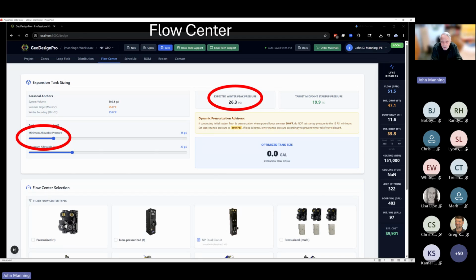And this is the nature of polyethylene pipe. And the program takes into account all the dynamics, the different modulus of elasticity for polyethylene over time. The program will also suggest a charging pressure. So if you're initially filling your system with neutral water temperatures and ground temperatures, might be 50 to 60 degrees, it will say, charge it to about 20 psi. And under these conditions, you don't need an expansion tank, which most engineers almost always want to put in. But if you're willing to let the pressure fluctuate from 15 to 27 psi, you don't need an expansion tank.